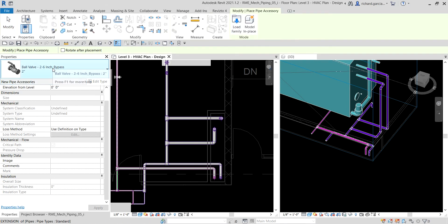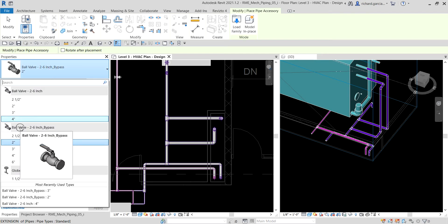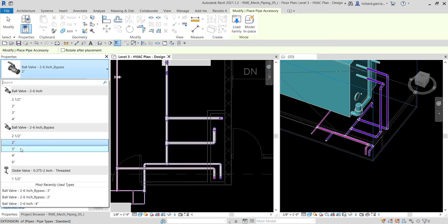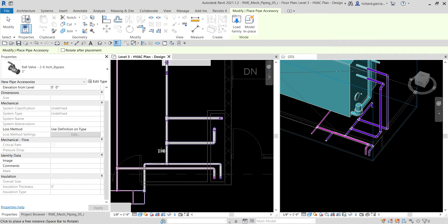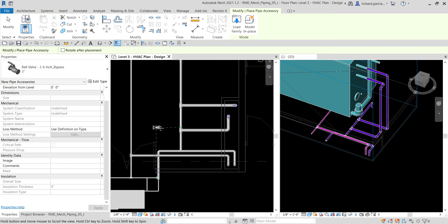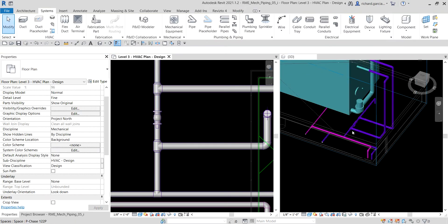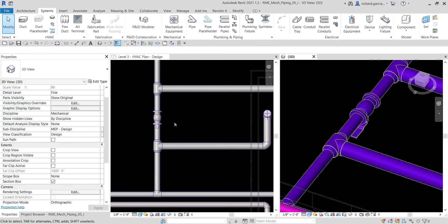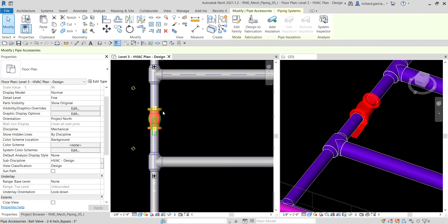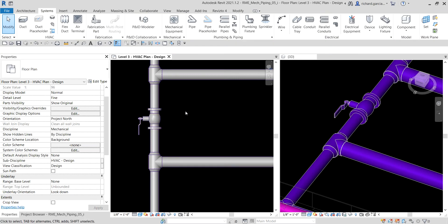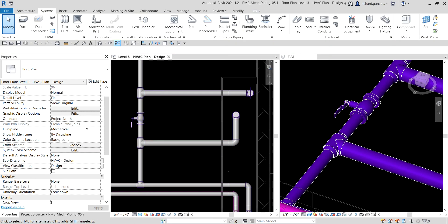Let's look for the bypass valve — the ball valve two to six inches bypass. We are going to use three inches. By the way, the bypass valve is closed by default. I'm going to hover my pointer to this pipe here and then just click to place it. Then select Modify. That's our valve. Now let us rotate the bypass valve — select this valve and click the rotate icon. Then click on the blank space to deselect the valve.